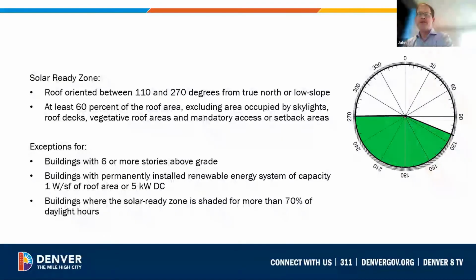The code requires that a zone designated for availability of solar photovoltaic panels, or PV, be indicated on the construction drawings. Now, I want to distinguish a solar-ready zone from the solar itself. While there is no mandate for rooftop PV, an area that is 60% of the free roof area, which would exclude setbacks and designated spaces for rooftop HVAC equipment, must be available for solar panels. Existing shading from neighboring structures that would cause the roof to be shaded for the majority of the daylight hours triggers an exception for this requirement.